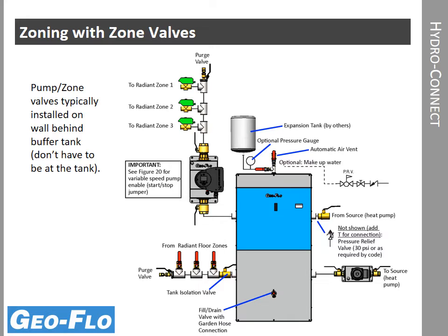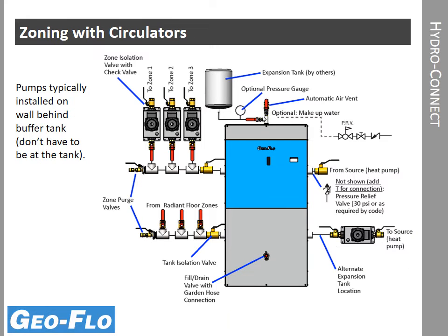This is certainly the most efficient way to go. With a hydronic system like this, the pump will only deliver the flow necessary for each of those zones. Likewise, if we're zoning with circulators, it also only delivers the flow for that zone. However, we have a lot more watts required when we're zoning with pumps individually rather than a variable speed pump with zone valves. That gives us the advantage of better efficiency. So either method is certainly a good way to go. It's more of a matter of the application itself and the goals from a standpoint of efficiency when we're looking at the hydronic side of the equation.